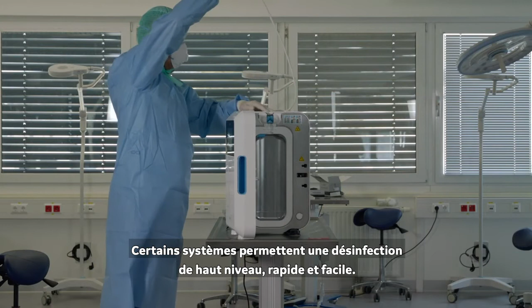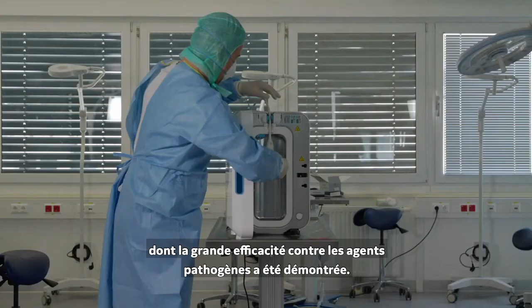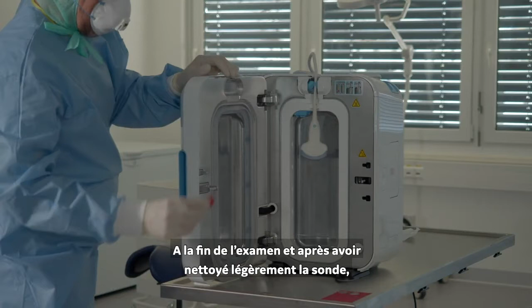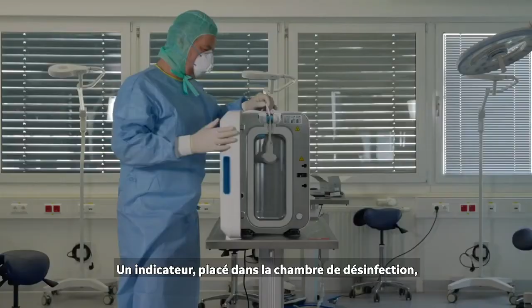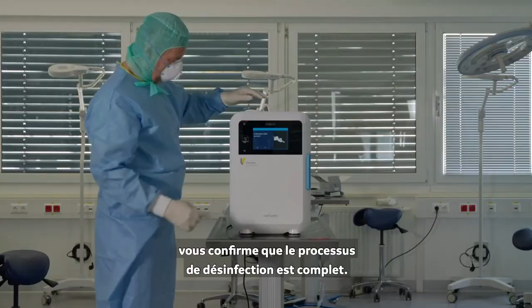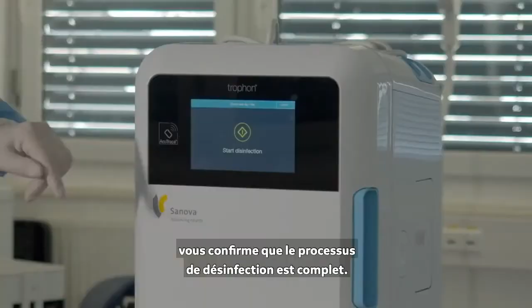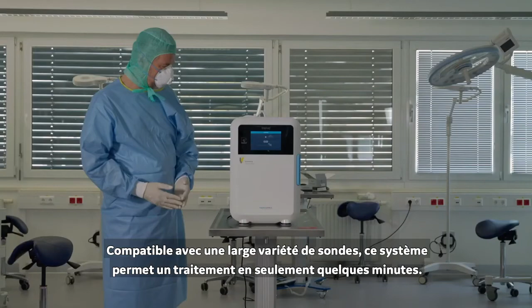Special systems are available for quick and easy high-level disinfection. Such systems use a vaporized hydrogen peroxide solution, which has been shown to be highly effective against pathogens. After examining a patient and roughly cleaning the probe, place it in the disinfection system. An indicator, which is placed into the system along with the probe, provides evidence that the disinfection process is complete. Accommodating a wide variety of probes, the system produces results within just a few minutes.